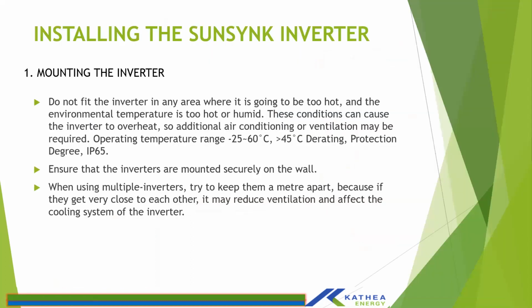So installing a Sunsynk inverter, the inverters are IP65, the protection degree. So the inverter can be installed outdoors as well. The operating temperature is around minus 25 to 60 degrees, which is basically within the temperatures of our region. And when the temperature gets more than 45 degrees, the inverter will start derating.